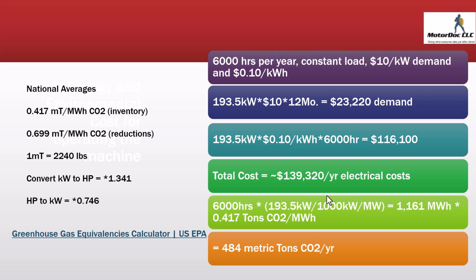So if I look at this application here, I have a machine operating 6,000 hours per year, $10 per kilowatt, and 10 cents per kilowatt hour because I'm lazy. And I take a look at this, 193.5 kilowatts, which was that previous machine. This gives me my demand charge, which is $10 per the peak times 12 months. And this one is the usage. So basically it comes out to be about $140,000 per year to operate that electric machine.